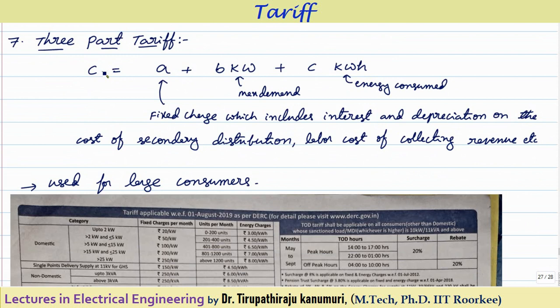The last one is three-part tariff, used for large consumers. Here the cost involves three parts: A is called the fixed charge, which includes interest and depreciation on the cost of secondary distribution, labor cost of collecting the revenue, etc. Then B times kilowatt is the maximum demand charge, and C times kilowatt-hour depends on the energy consumed. This maximum demand can be either in kilowatt or kVA. If you want to encourage the consumer to operate at higher power factor, keep it as kVA; if that is not a concern, then we can keep it as kilowatt.